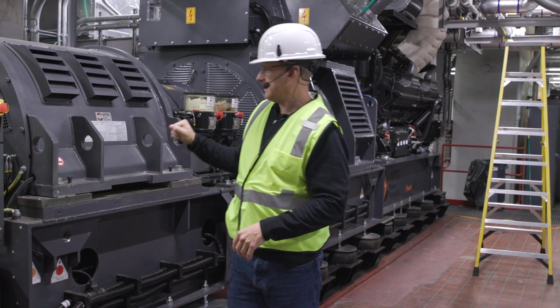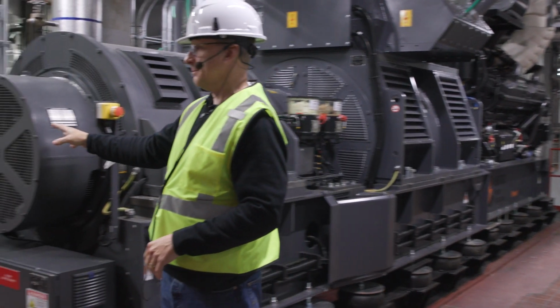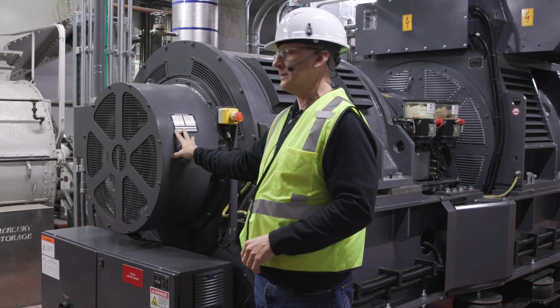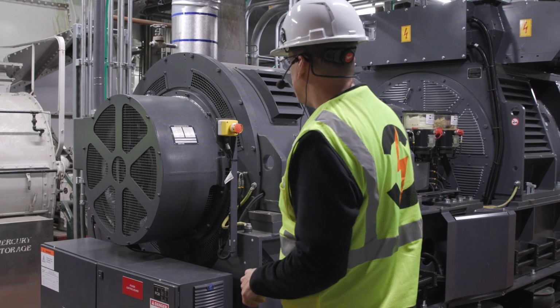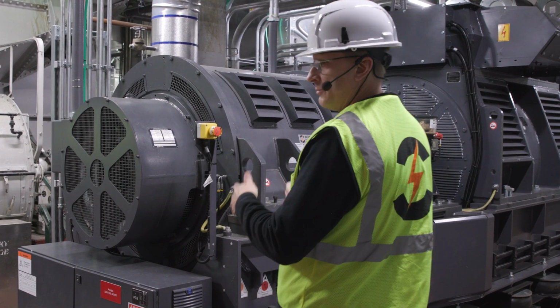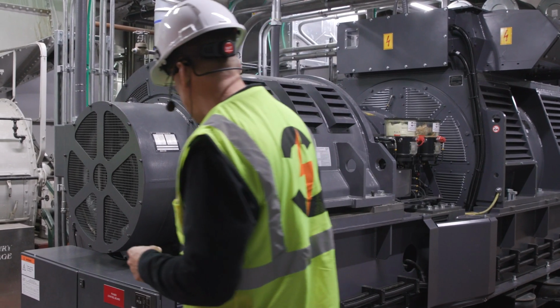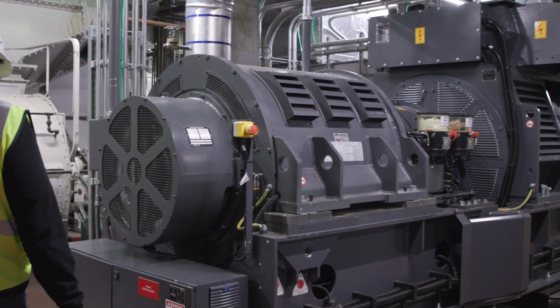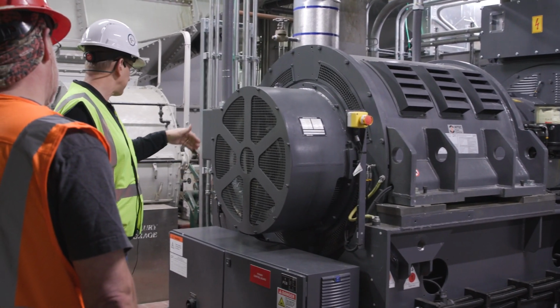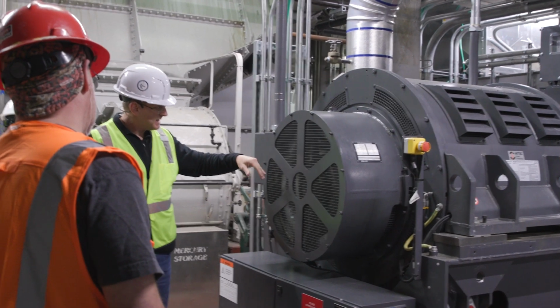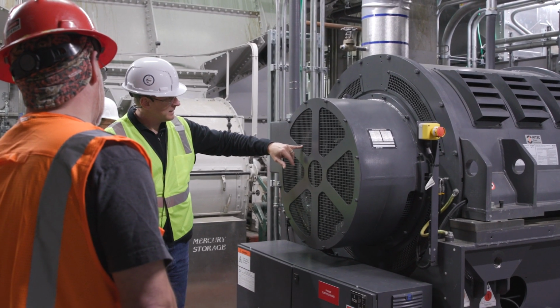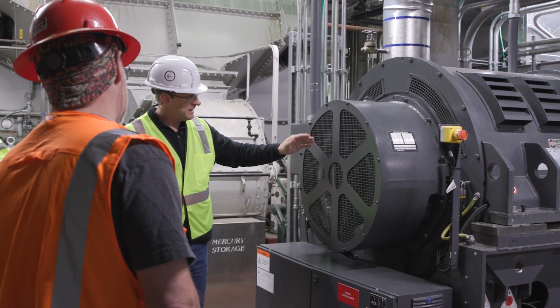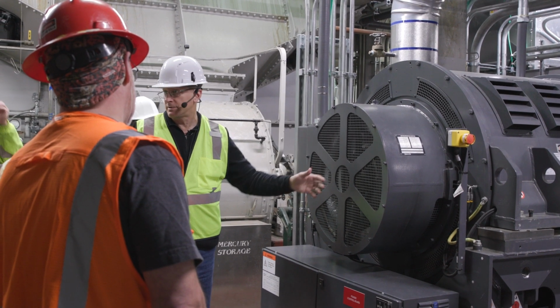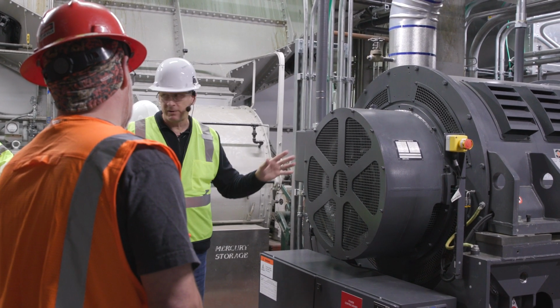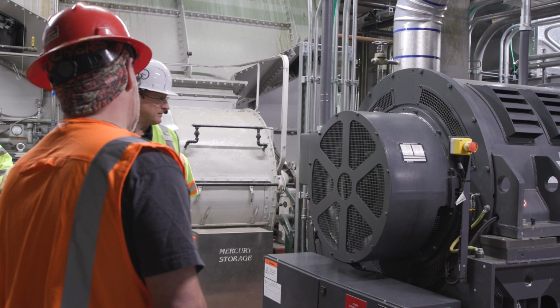And then on the other end, we've got our pony motor, our three-phase asynchronous motor that actually will spin the flywheel. And if this were to be spinning, you can actually see the inner rotor and the outer rotor, and you can see them spinning in relation to one another when the unit's running. Right now, of course, everything is at a standstill because it's off.